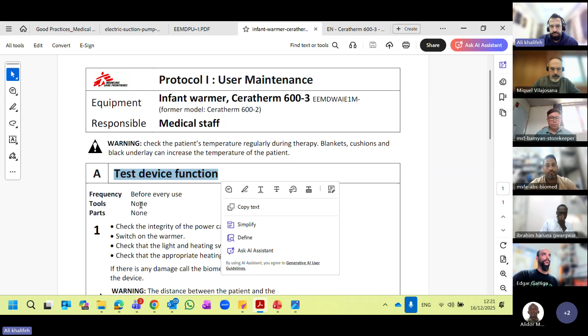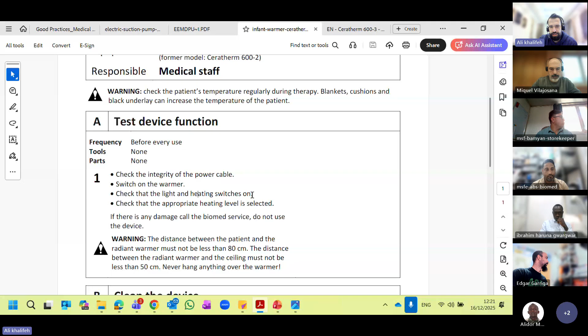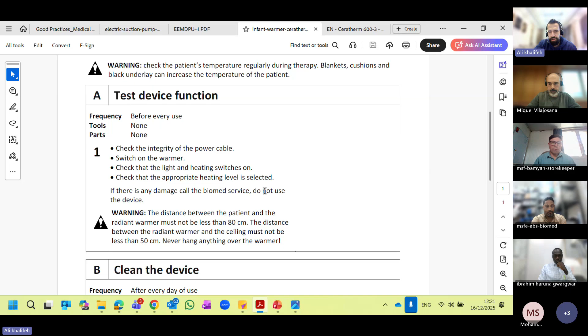Protocol one is usually the maintenance protocol for medical equipment. Here are the tasks they have to do. First, they have to test device function: before each use, check the integrity of the power cable, switch on the warmer, check the light and heating switch on, and check that the appropriate heating level is selected. If there is any damage, call the biomedical service and do not use the device.